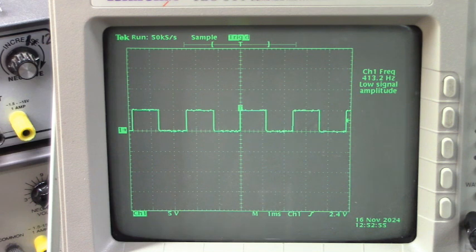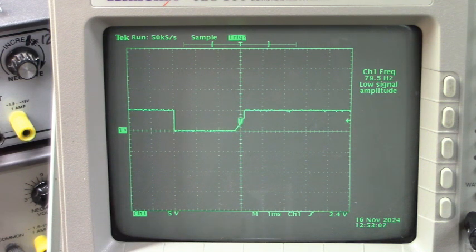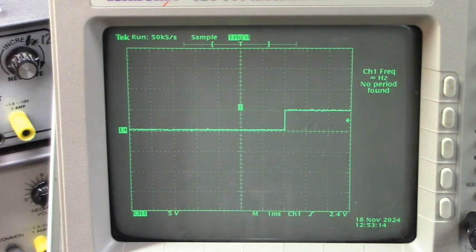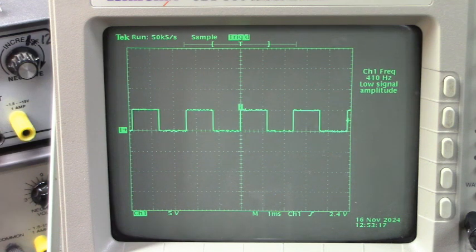That square wave output would be wider. Watch, I'll turn the cooling fan off and you see how that frequency is extended out, slowing down and stopped. Turn the cooling fan back on. There we go. All we have to do to fix that drive is get that smaller cooling fan because it doesn't spin. That'll take a couple of days.